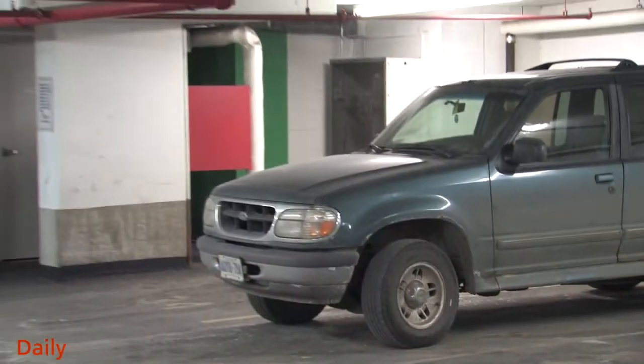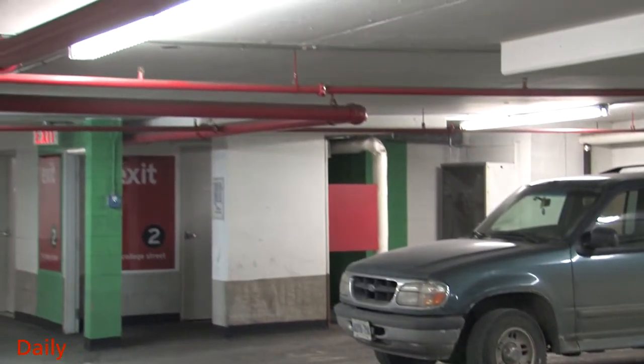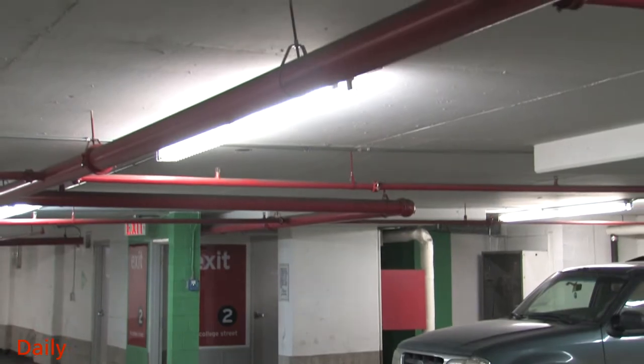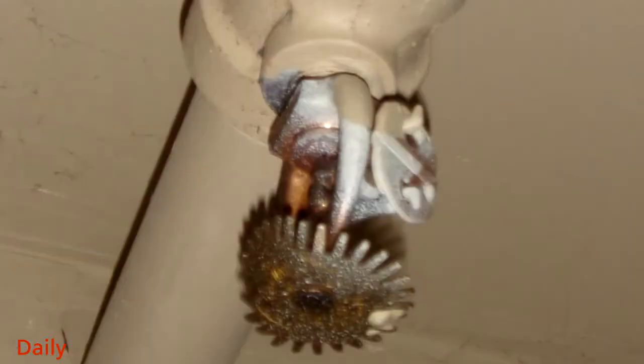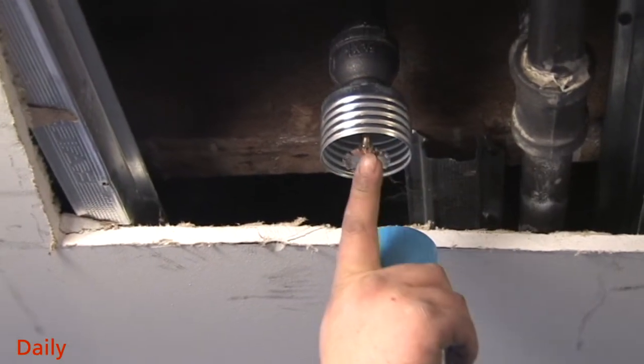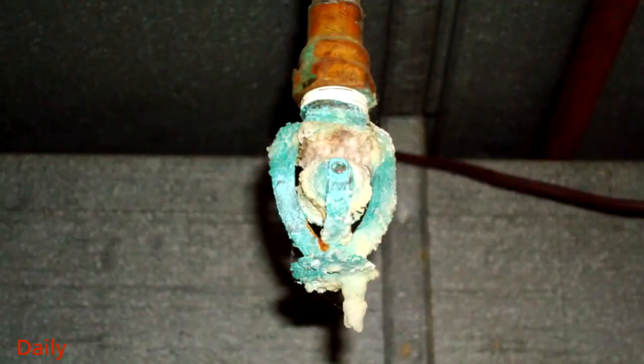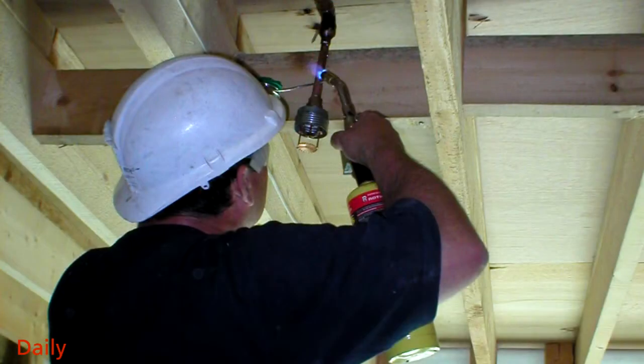Sprinkler heads and pipes in indoor parking garages can be easily damaged by tall vehicles or antennas. If damaged sprinkler heads are found, staff should notify the building's fire protection contractor. They will assess the equipment and advise you if the fire department requires notification that the system is impaired or out of service. They will also ensure any defective heads are replaced.